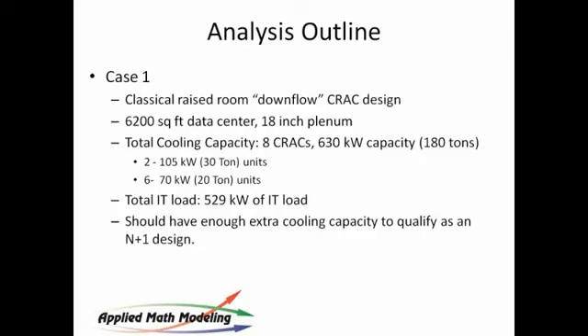Now we have 2 different kinds of units in the room. We have 20-ton units and 30-ton units. What modeling allows you to do is understand what happens depending on which one fails, because the things do change. Airflow is very hard to predict without a modeler, and you can't just look at it and say, well, this is going to be fine. Rules of thumb are fairly good in many cases. Here it's very helpful to have a tool that allows you to look at these designs closely.